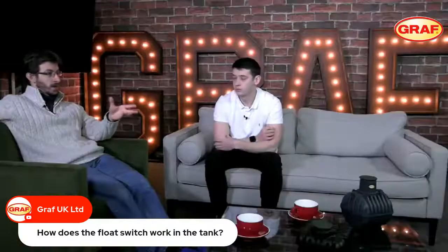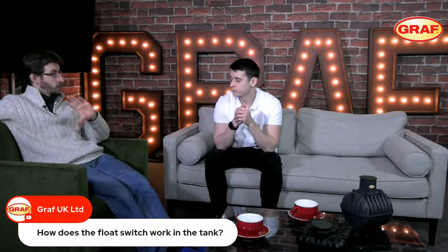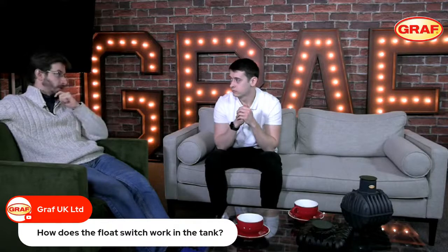If, however, we start running low on rainwater in an underground tank, the float switch will drop. And as with any switch, once the switch drops, it says, alert, we need to do something about this. And in this case, of course, we're saying we need to supply mains water in some form as a mains water backup. Now, depending on the type of system you may have, whether it be one of our wall-mounted pump kiosks, or if it's a submersible pump solution with a mains water top-up unit, the float switch will do that control automatically, and you're basically ensuring you've always got either rain or mains water going through the system to the appliances when required. So the float switch is there for the automatic control of rain and mains water to always ensure that the customer has some form of water going to their appliances.